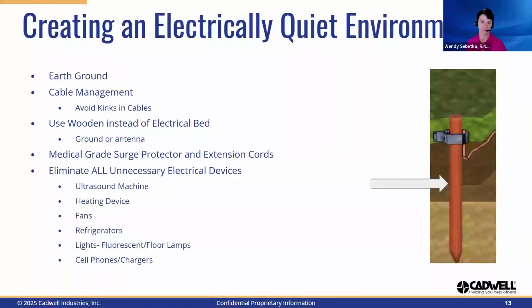However, in medical facilities, the resistance level is often recommended to be at or below 0.1 or 0.2 ohms due to the sensitivity of the devices. Ground resistance testing can be performed by an electrical professional using a ground resistance or an earth tester.